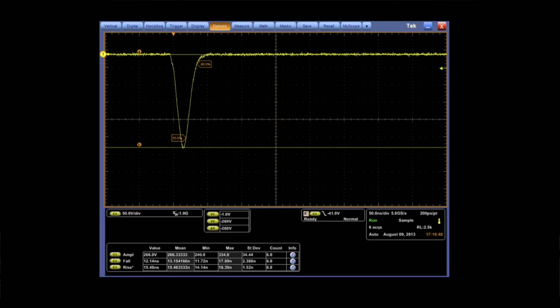The pulser works in concert with the voltage. The higher the voltage we get, the more oomph we get from the signal, at the expense of using more battery power and maybe a little bit more wear and tear on your transducer. If you select spike, it sends a very short negative voltage spike to the transducer. Now, it's not infinitesimally short. It does take a very short amount of time to rise and a little bit longer to fall. But for the purposes of illustration, we'll consider a spike short and sharp.